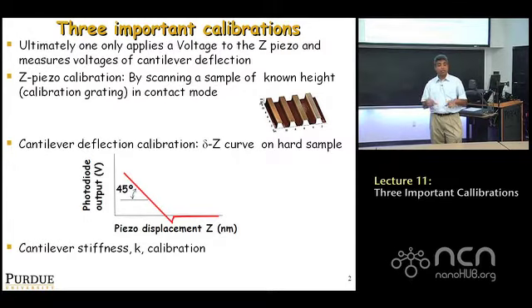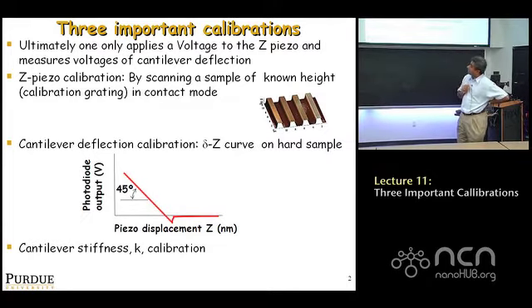Same thing with your XY piezos. When you scan, you're moving in the X and Y direction of the piezo, and those images come in nanometers. Well, how do you know that truly is the right nanometer? Because really what the system does is apply a 10 volt sawtooth wave to just scan the sample back and forth. But how do you know that it is moving as much as advertised, or as it appears in the images? So that's what the Z-piezo calibration is really about.